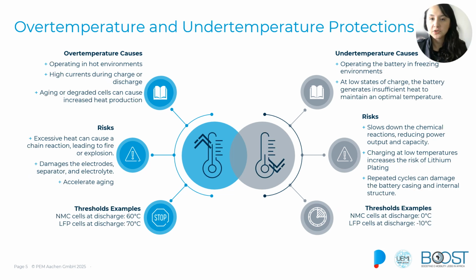We also have protections for the temperature: over temperature and under temperature protections. The over temperature occurs when the battery cells exceed their maximum safe temperatures, which can happen due to different factors. This can happen, for instance, if the battery is operating in a hot environment or very close to heat sources, like fire or another system that is heating up. Additionally, high currents during charging or discharging will also generate heat, because, as you remember, the battery has an internal resistance, and that internal resistance will generate some heat because of the power that it is dissipating.